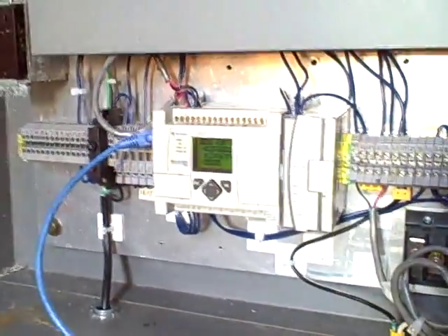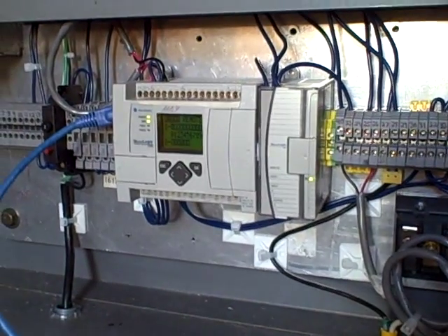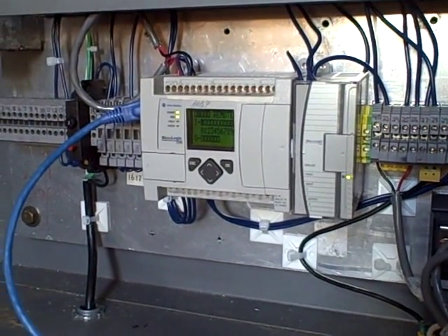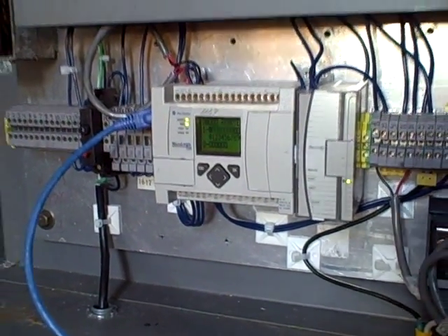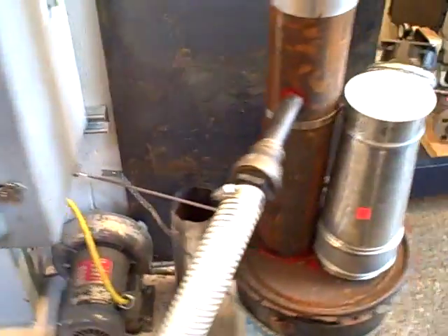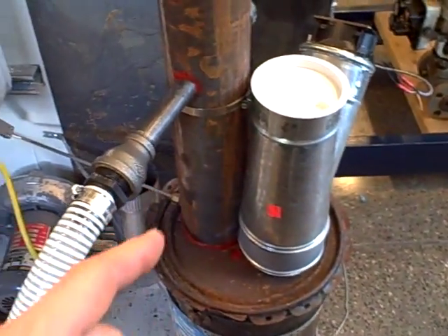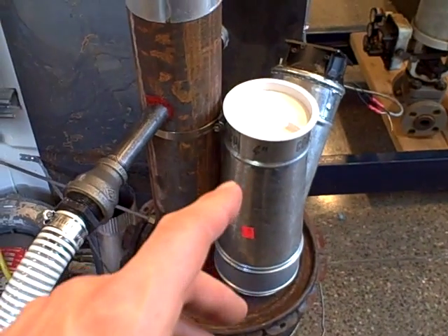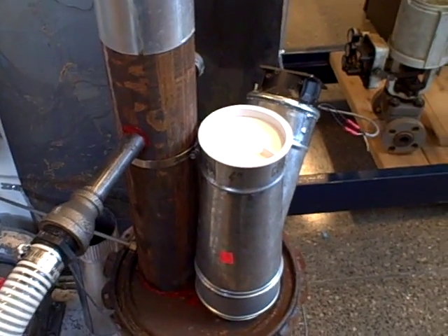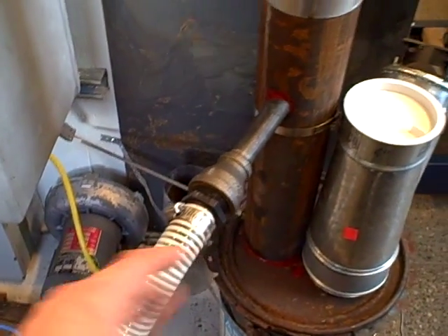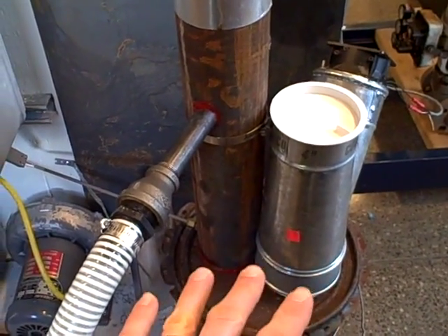be of that signal. Our next step is to take the PLC and program into it a timer and counter routine where it counts how many pulses per second, and based on that it's going to determine a flow rate of air into the rocket stove. Our first phase of using this flow meter is going to be doing PID control based on flow, so we can establish a flow set point and then have the PLC control the speed of the motor to get the flow that we want to the rocket stove for precise flow.